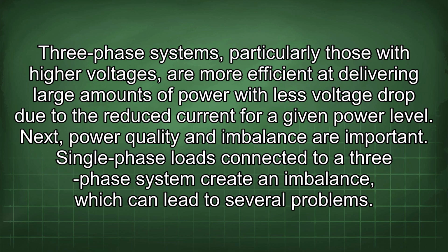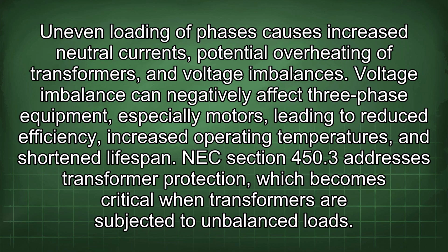Next, power quality and imbalance are important. Single-phase loads connected to a three-phase system create an imbalance, which can lead to several problems. Uneven loading of phases causes increased neutral currents, potential overheating of transformers, and voltage imbalances. Voltage imbalance can negatively affect three-phase equipment, especially motors, leading to reduced efficiency, increased operating temperatures, and shortened lifespan. NEC section 450.3 addresses transformer protection, which becomes critical when transformers are subjected to imbalanced loads.